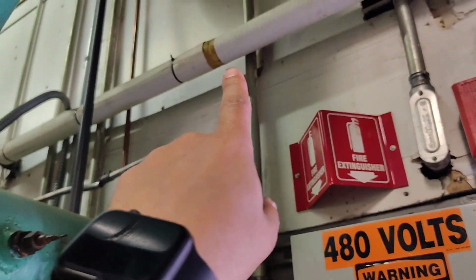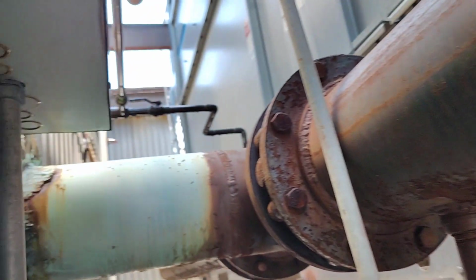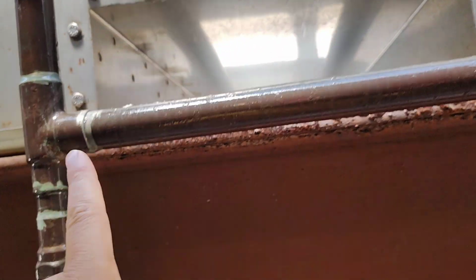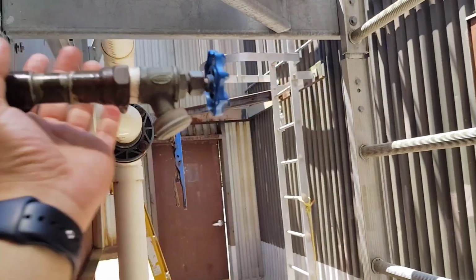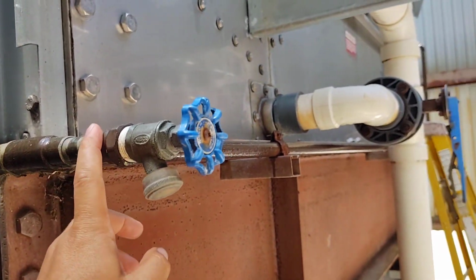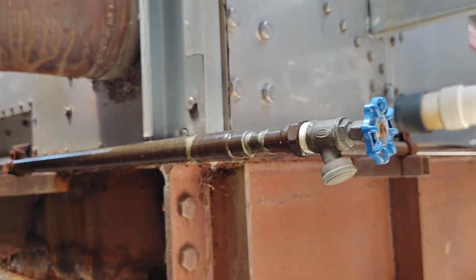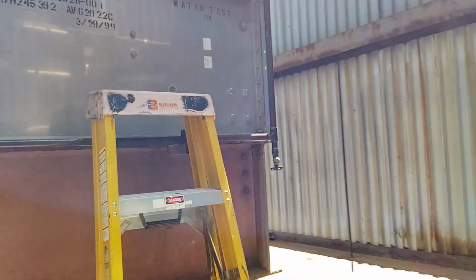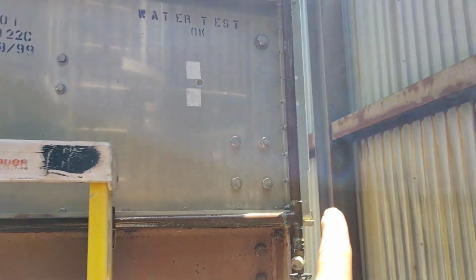And this one, and let's go here. It's going to the cooling tower. It's coming from here, the side, as we see. It's giving this side and giving this side. You know, all the valves are open. It's giving this side here. Okay, there is one drain here. We are following the right one. There is a drain here. Okay, at this 90 degree, there is this drain, and we are continuing here. We will meet another 90 degrees here, so it must be the drain, and this is the makeup water supply.